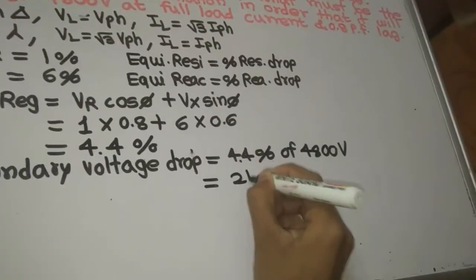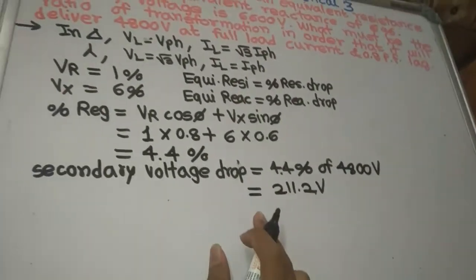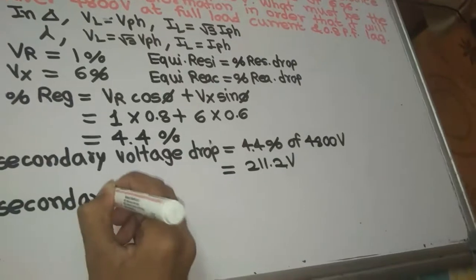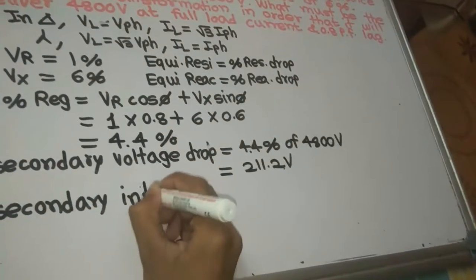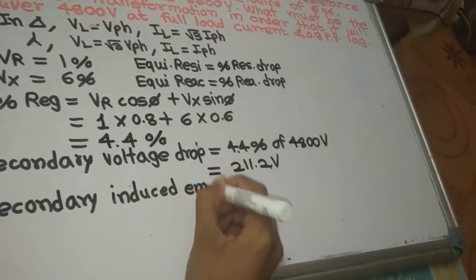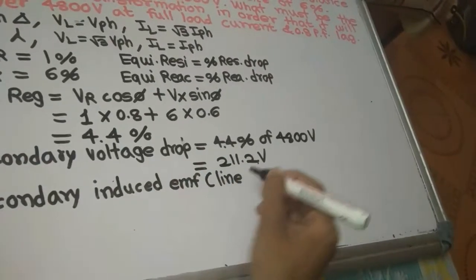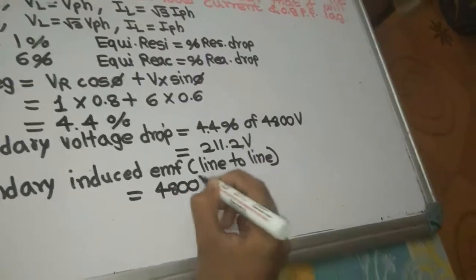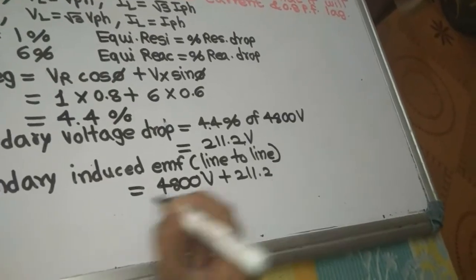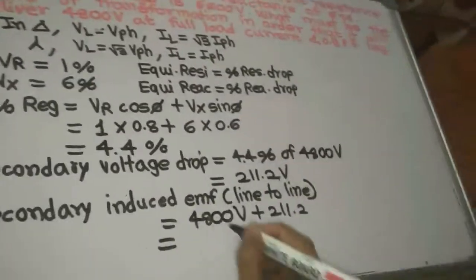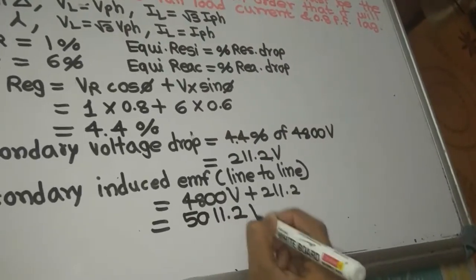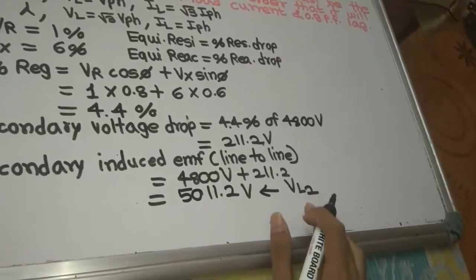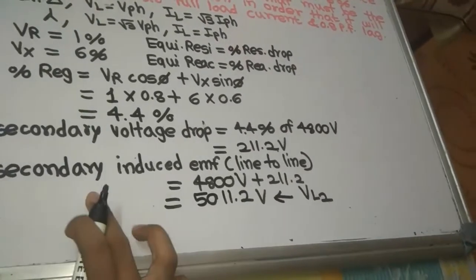4.4% of 4800 volt = 211.2 volt. This is the secondary voltage drop. So secondary induced EMF (line-to-line) = 4800 + 211.2 = 5011.2 volt. This is VL2, the line voltage on the secondary side.